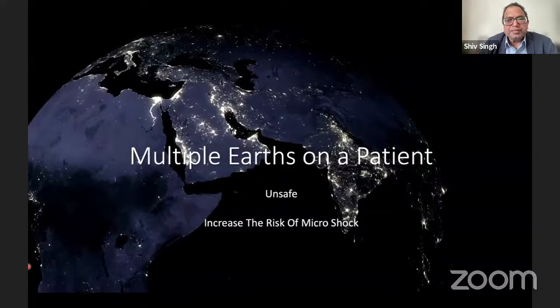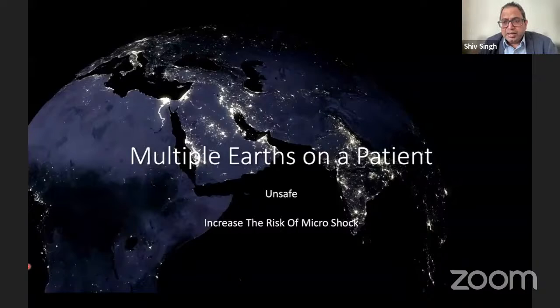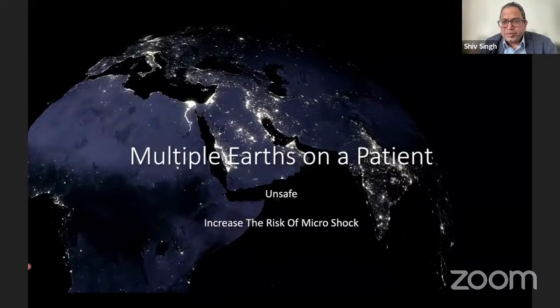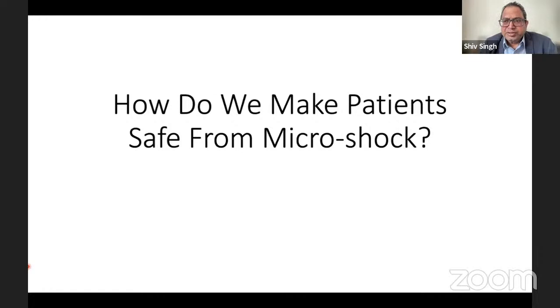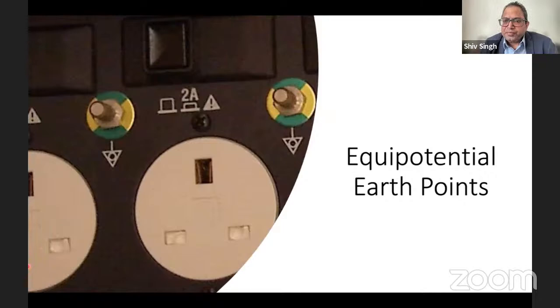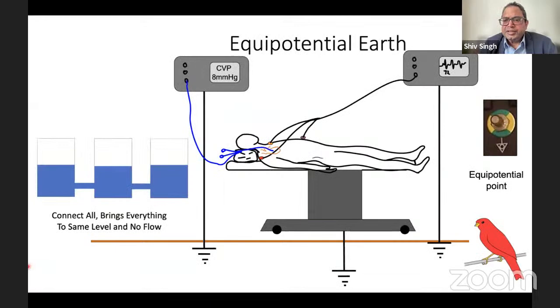Now we do use equipment which has got isolated power, but if for any chance we detect that there are multiple earths and it's impossible to actually keep the patient earth-free, that's where the equipotential earth points come in. So you see these equipotential earth points everywhere. Theaters should have them, and machines actually have them on the back.